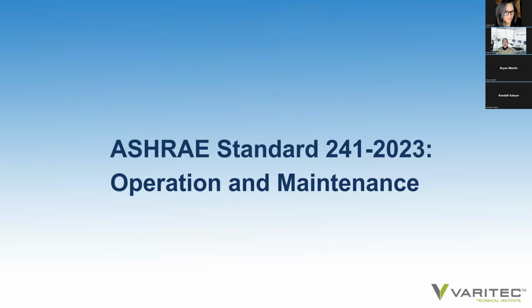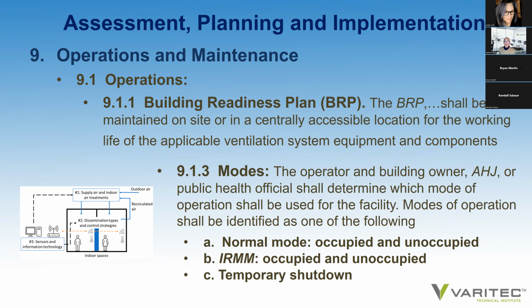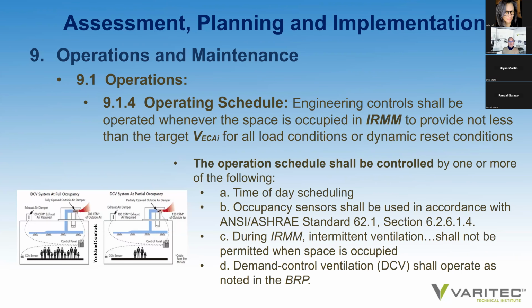So, operation and maintenance: there are guidelines for operating building readiness plans in the building. Section 9 on operations and maintenance says that there are modes of operation that need to be addressed and assessed, and that need to be provided to the authority having jurisdiction. There's normal mode, there's infection risk management mode, and then what happens to a building when it goes into temporary shutdown. There are operating schedules to be provided and to be validated that they're being maintained. All of this will have to be documented. And it goes on in this section to explain flush cycles between occupied periods, occupant count during infection risk management mode, operation of various fan speeds, etc. All of this is available in the standard. There's also a section 10 on dwelling units that we just don't have time to go into today.